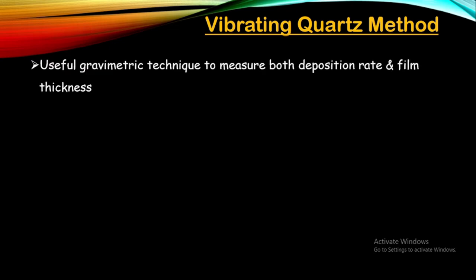This vibrating quartz method is a very useful gravimetric technique to measure both deposition rate as well as film thickness, and it involves a quartz crystal oscillator. Gravimetric means relating to the measurement of weight. The quartz crystal microbalance used in this method is an extremely sensitive mass balance which can measure nanogram to microgram level changes in mass per unit area — so even a minute change in mass is going to be recorded.